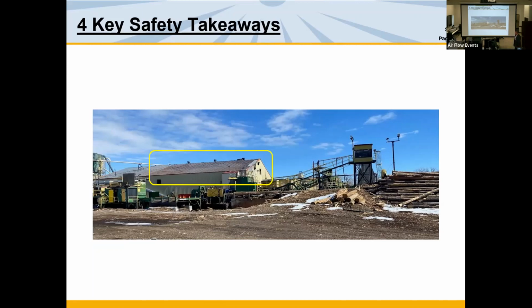I want 4 takeaways on safety, okay? And I want to scare people with infrared. I don't want to scare people with heating, with gas, but you got to think. And the ones that typically I end up going to fire losses, and I do that about once a year, it's usually somebody trying to do something on the cheap. They don't want to buy the right vent kits. They want to buy more heat than they need. They don't get asked the right questions, and they do really shoddy work. Almost every time the problem comes down to finding a cheap contractor that nobody else is willing to work with, and bad work gets done. So I'll show you the slides that I want the takeaways from. Next slide.